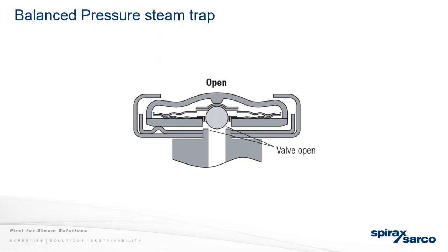So again, this is the capsule that's inside. This is the area that expands. As it does, it pushes down the ball. These are a replaceable part. Obviously, because you have metal that is expanding and contracting, it has a lifespan, but it's a relatively simple thing to replace.